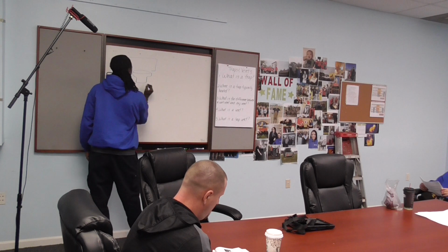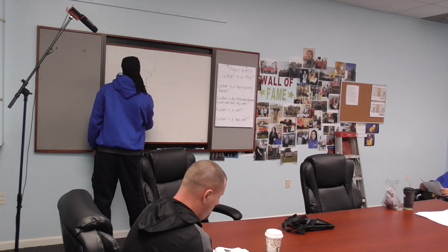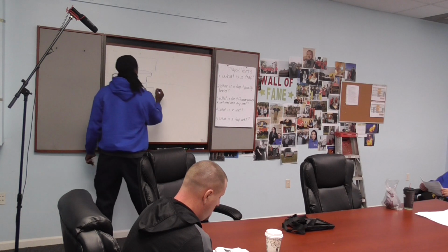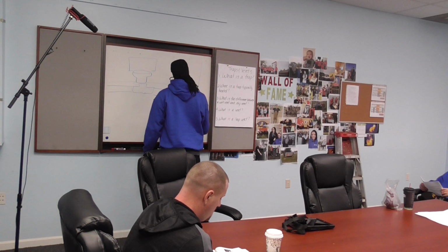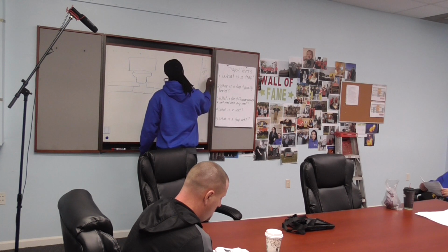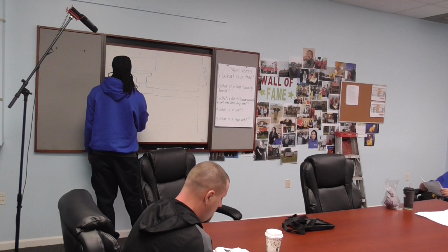And you have your drain here, and this is the floor, and then you have your drain coming under the floor, or whatever. And you vent it way over here. So this is the vent right here. Typically, it has to be 4 times the pipe size.